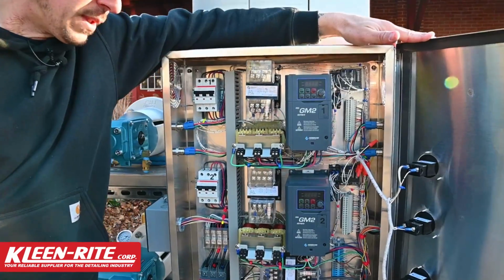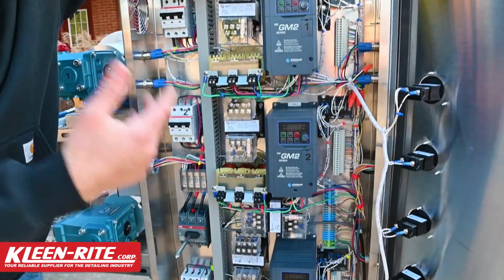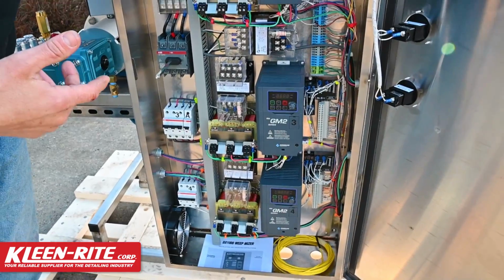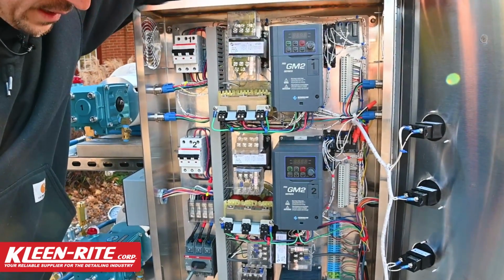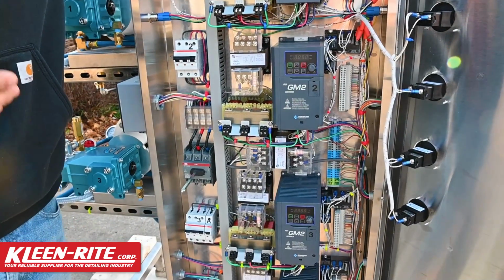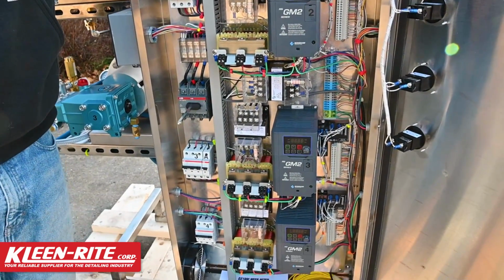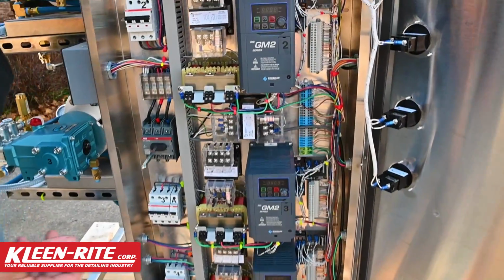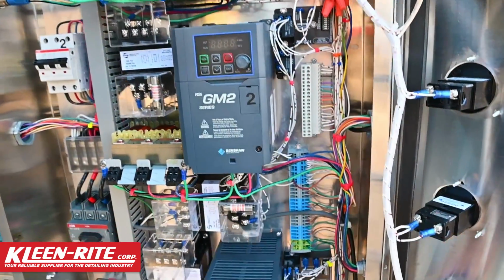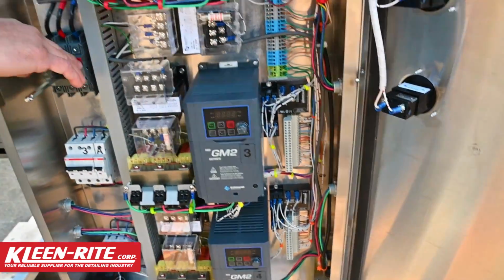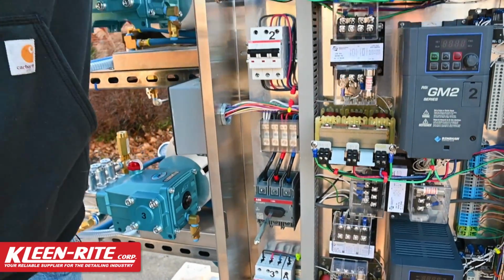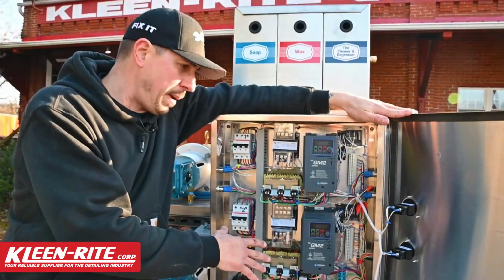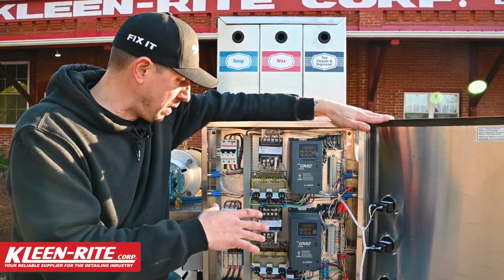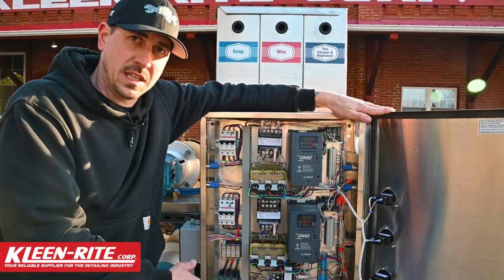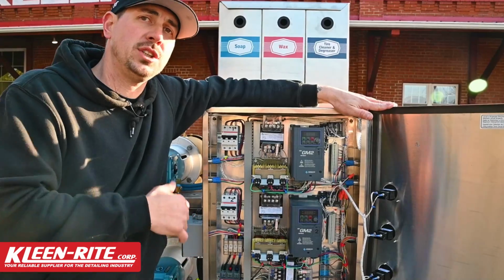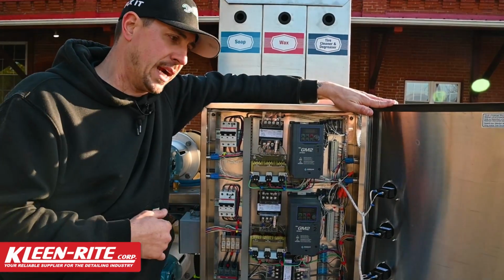So inside the main electrical cabinet, we have all the VFDs, all of our transformers, fuses, disconnects. We have a main disconnect. This unit comes pre-wired for everything. All you need to do is hook up main power and your bay wiring. All of your bay wiring is done on the right-hand side here, and your main power comes into the main disconnect. Now, we have a main disconnect to control all the power inside the cabinet to this unit, but we also have bay-specific disconnects so that if you for some reason do need to shut just one bay down, you don't have to shut the entire wash down.